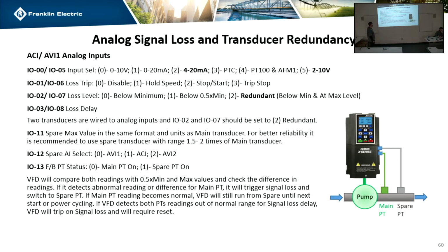So it compares both readings with the minimum and the maximum values, and it checks the differences in the two. If it detects that it's abnormal or different from the primary transducer, it triggers a signal loss, and it'll switch to the other one. If the main one then becomes more normal, like if you replace it, it'll run from the spare unit until the next start or power cycle, and it will do a check again, and it'll go back to the primary. If it detects that they're out of normal range, it'll fully trip on signal loss, and you'll have to reset it.